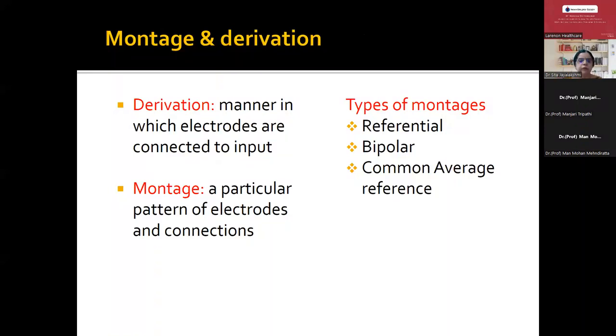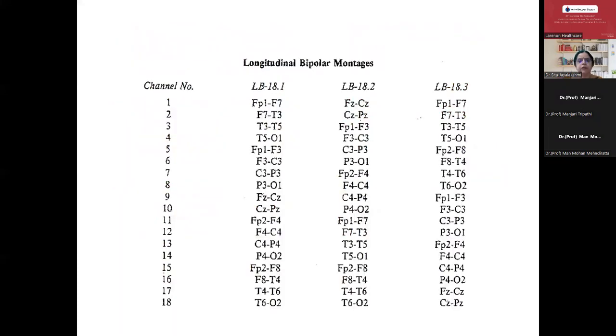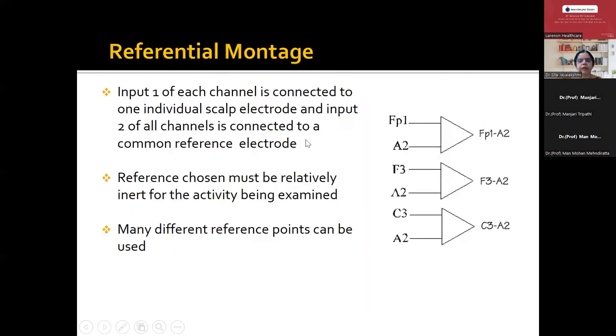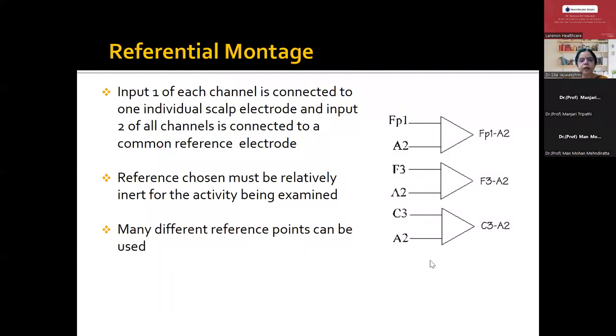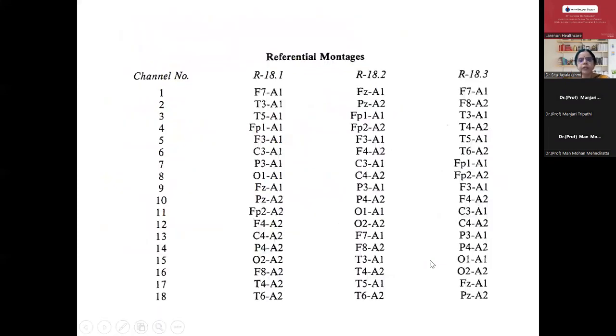Once we start recording, we should know about montages and derivations of the EEG. Derivation is the manner in which the electrodes are connected to the input. Montage is the particular pattern of electrodes and their connections. We have referential montage, bipolar montage, and common average montage. The longitudinal bipolar montage — the so-called double banana montage — is what we use very regularly. The referential montage has one electrode, usually A1 or A2, connected to all other electrode inputs. In the referential montage, localization is by amplitude — wherever it is maximum, that is the maximum surface negativity closest to the epileptiform activity.